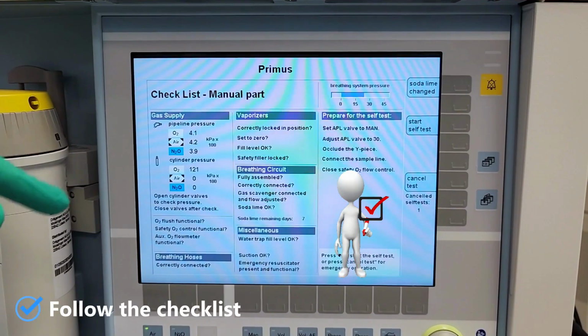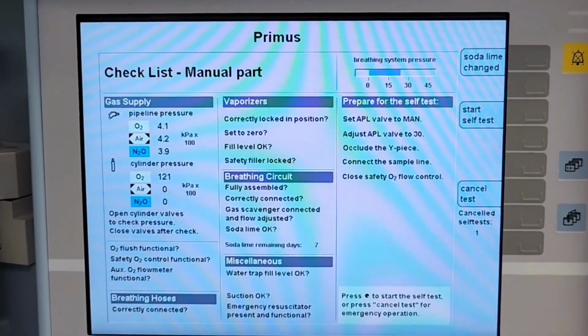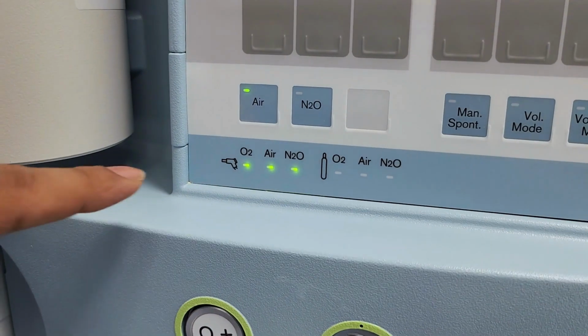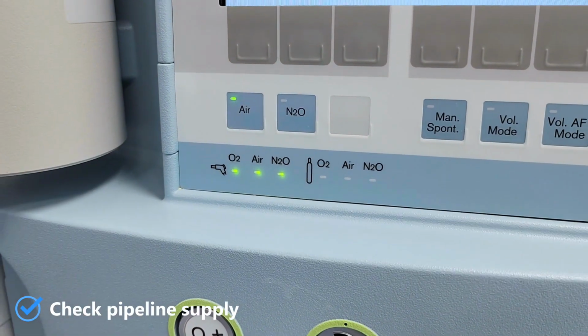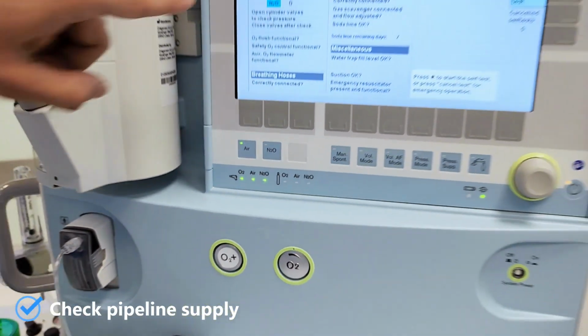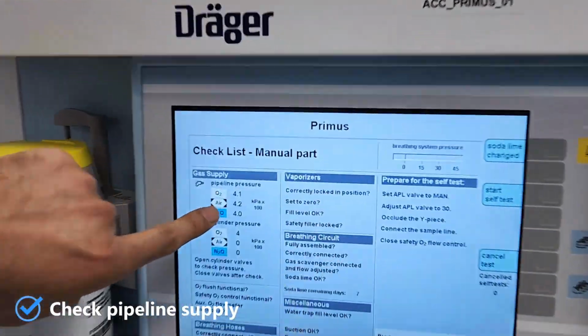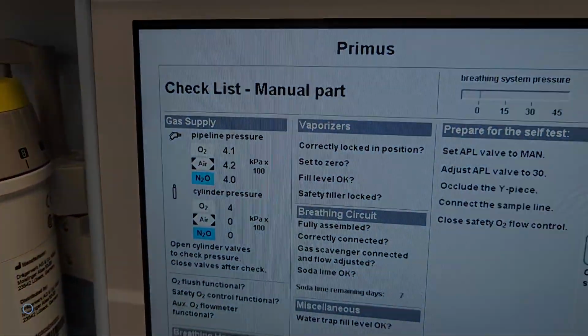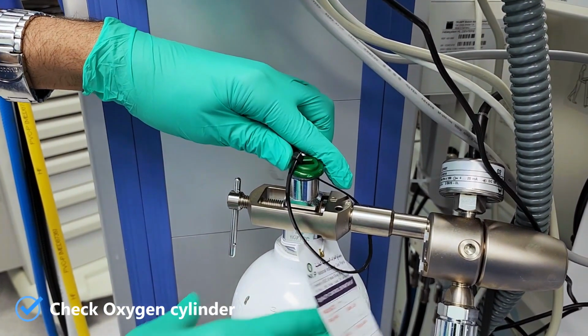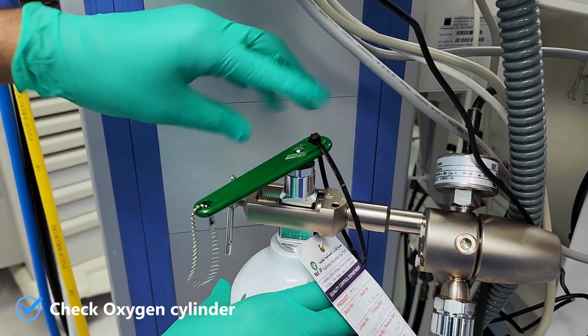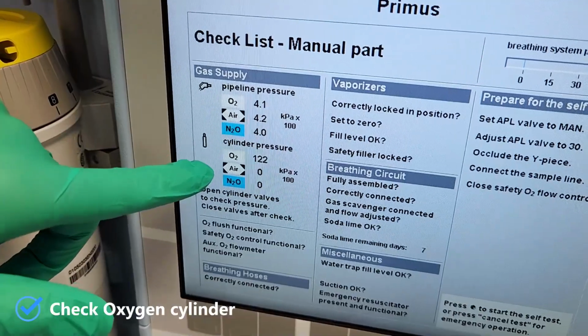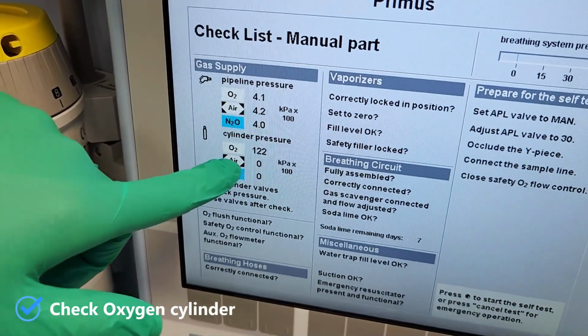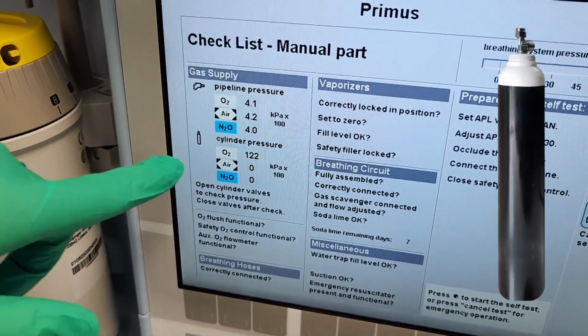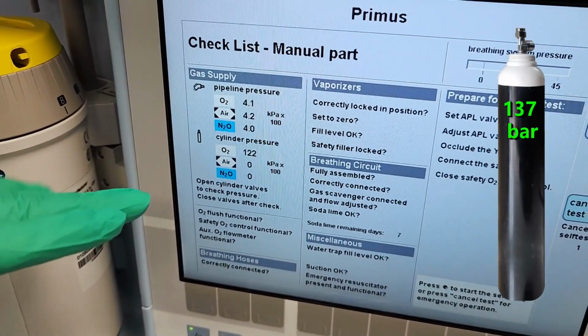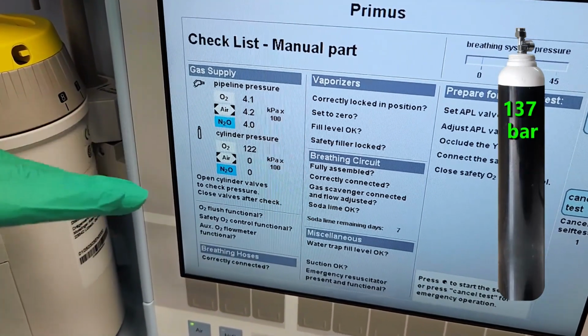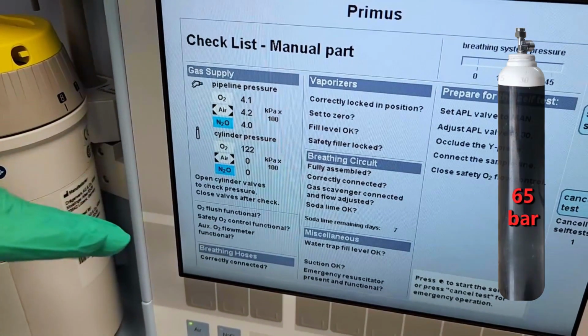For example, the first one is about gas supply. These solid green LED indicators confirm that the pipeline of oxygen, air, and nitrous oxide are connected and pressure is sufficient. The pipeline pressure can be seen on the main screen. To check the oxygen cylinder, turn the cylinder valve anti-clockwise. The LED indicators should be green. The cylinder pressure can be seen on the main screen. A full E-size oxygen cylinder will read 137 bar. The oxygen cylinder has to be changed if the pressure goes down below half.